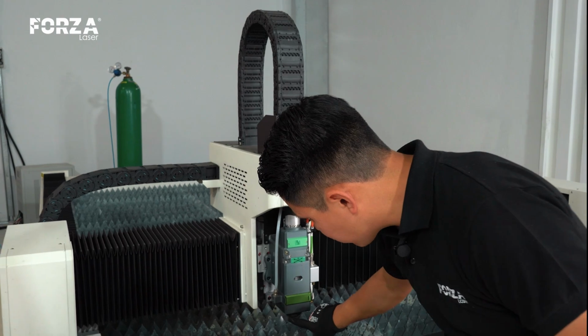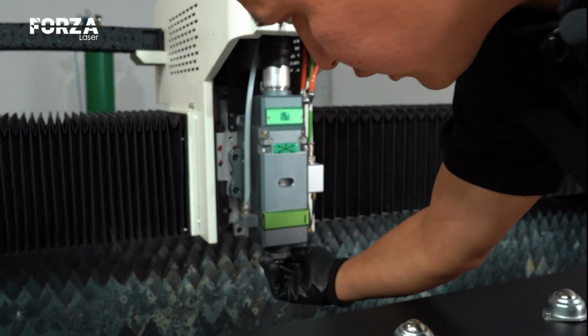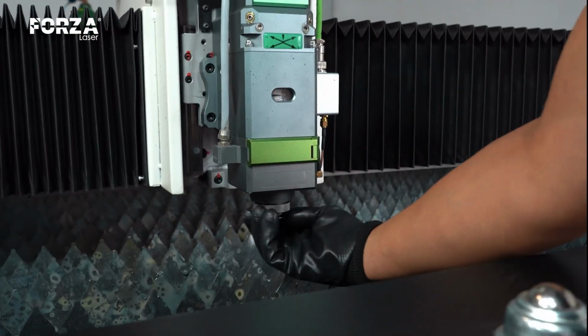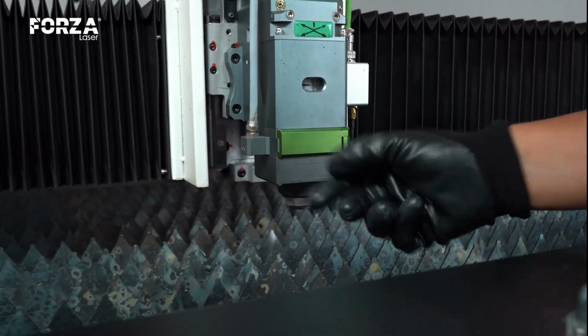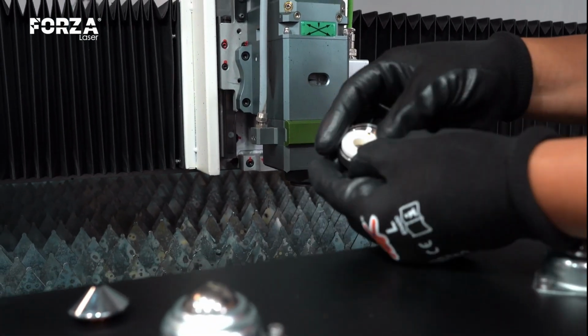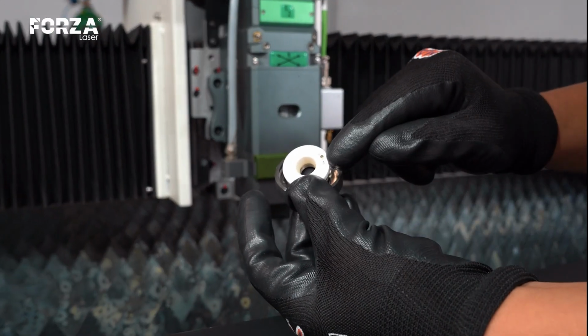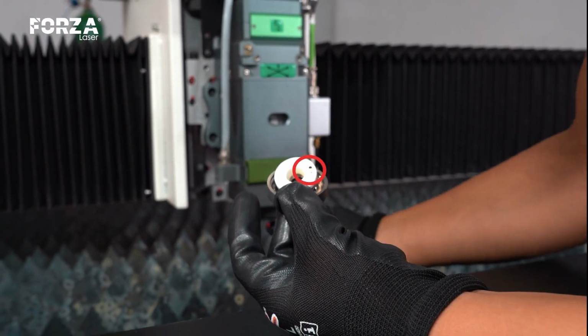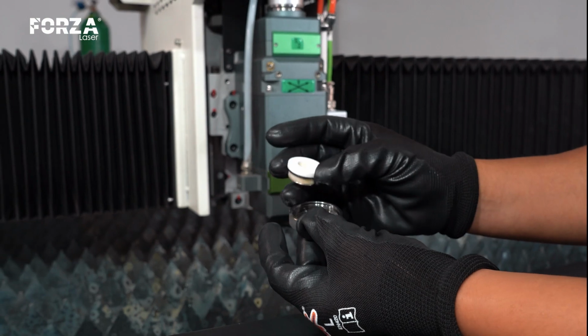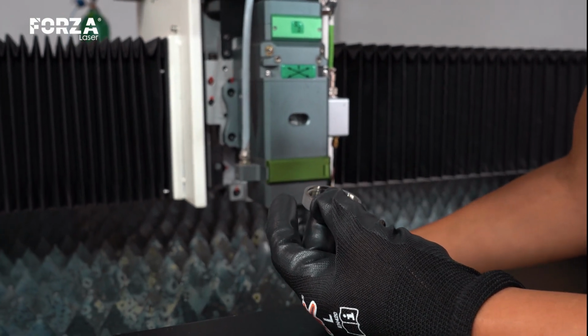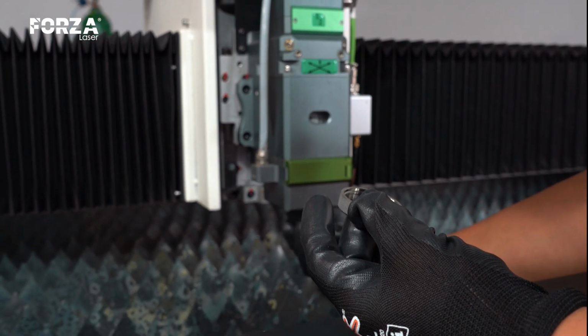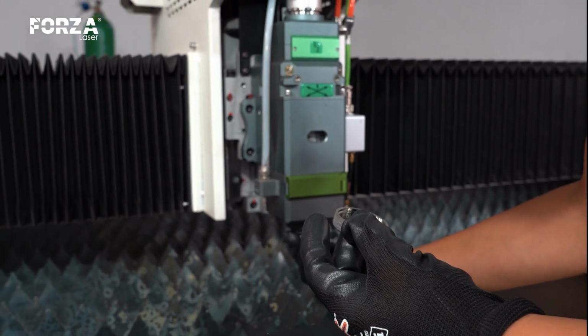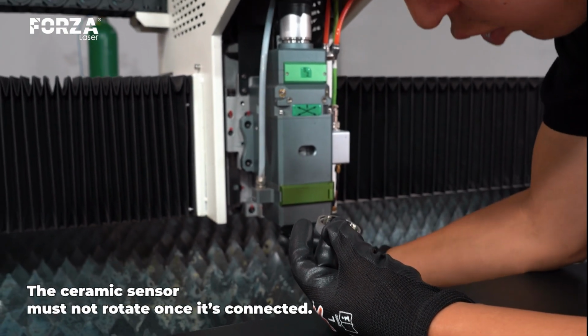Well, we have to loosen the locking nut that holds the sensor, remove the nozzle, loosen it, and check the ceramic base. Here's the ceramic base. These couplings connect internally here, and you need to place them correctly. For example, we'll find them here, make sure it doesn't rotate, and then proceed to tighten it.